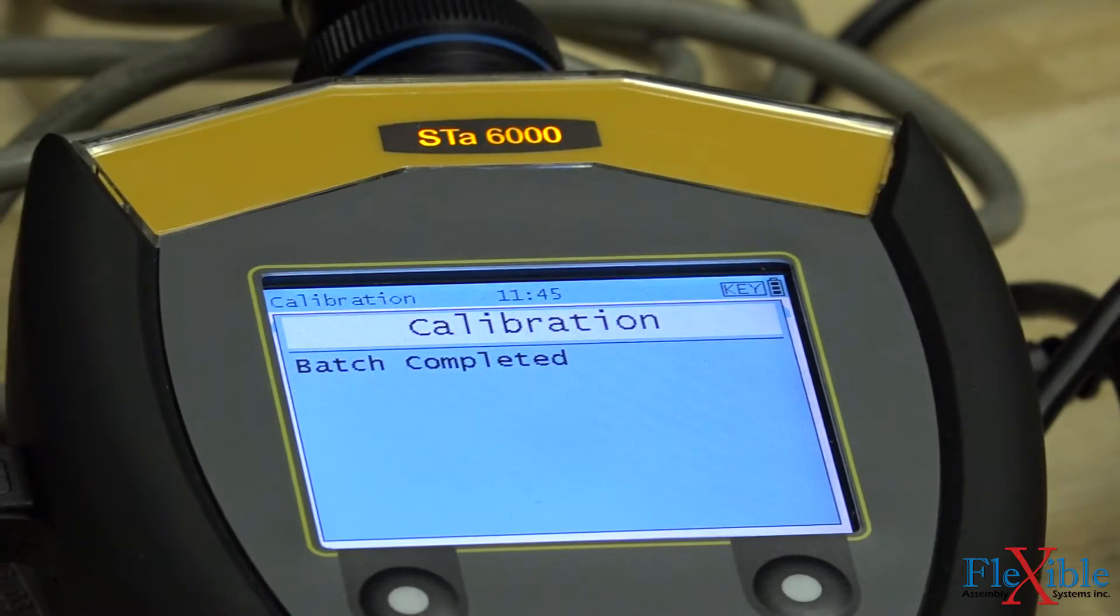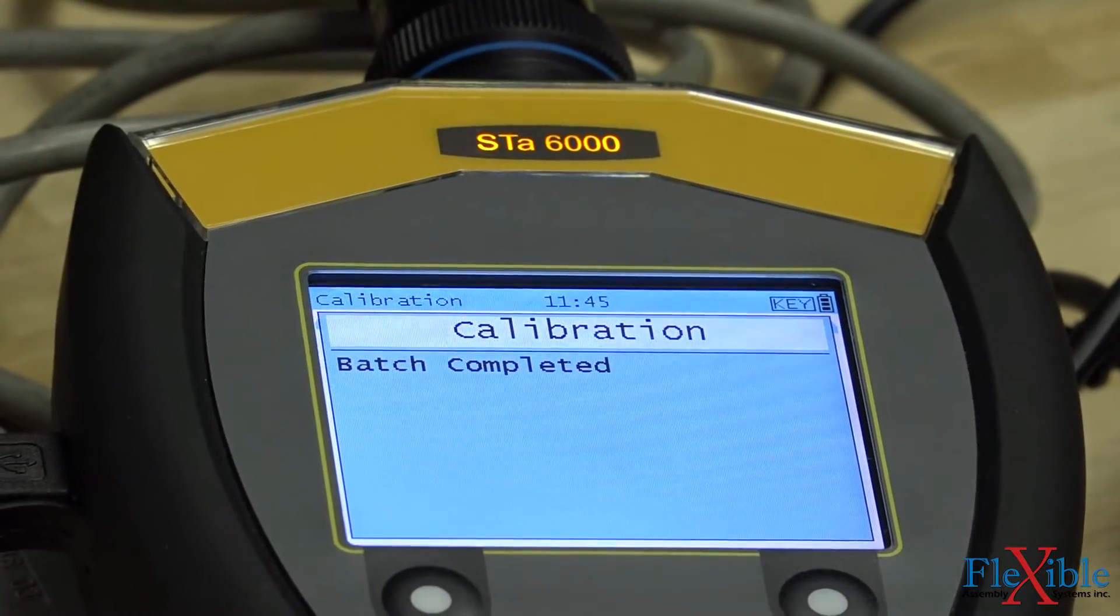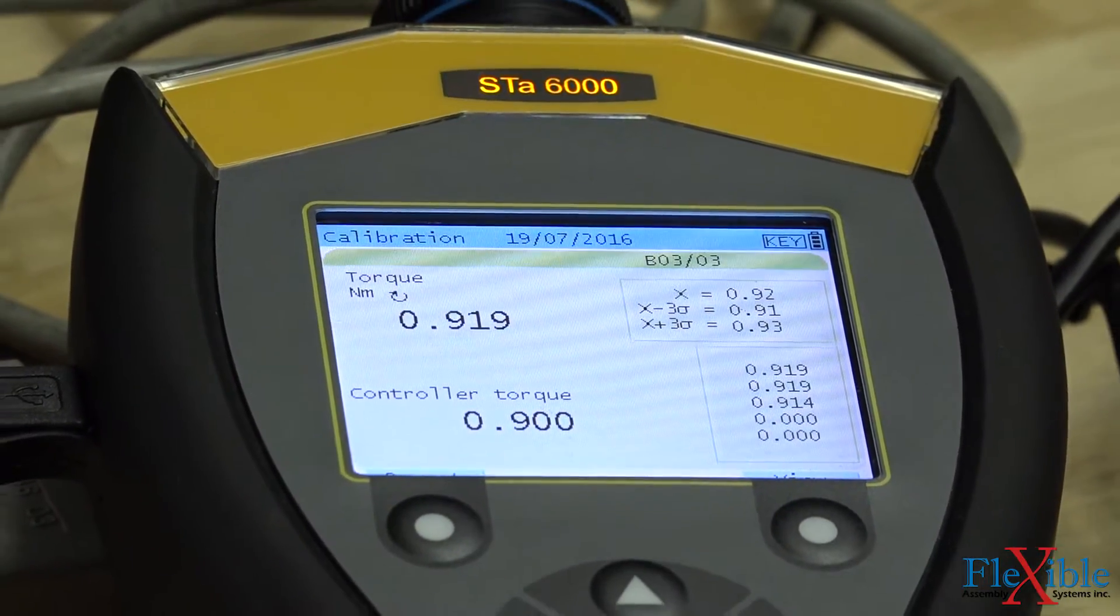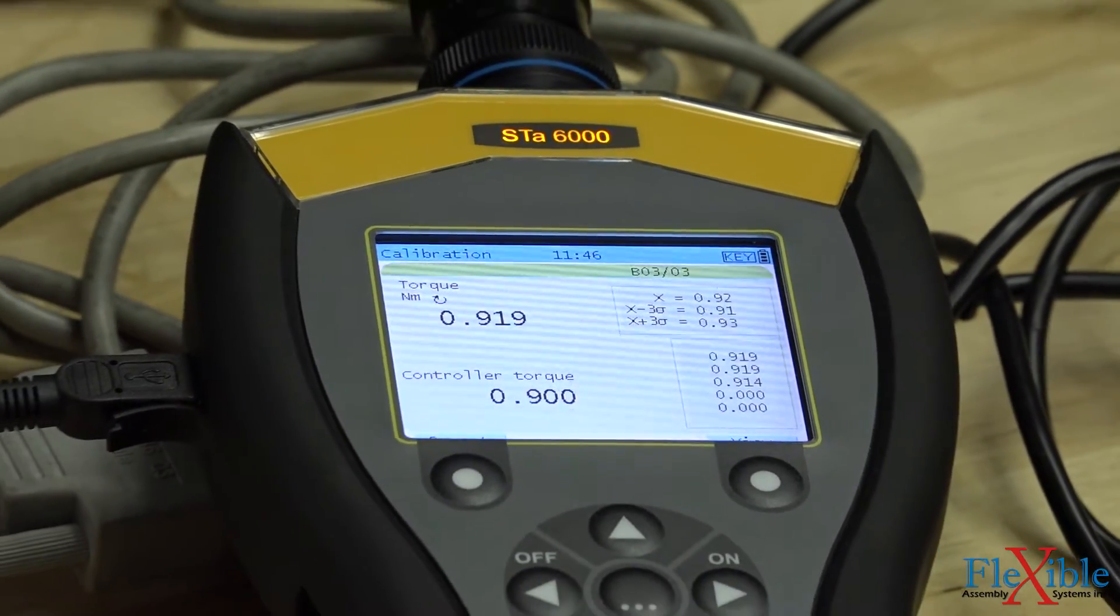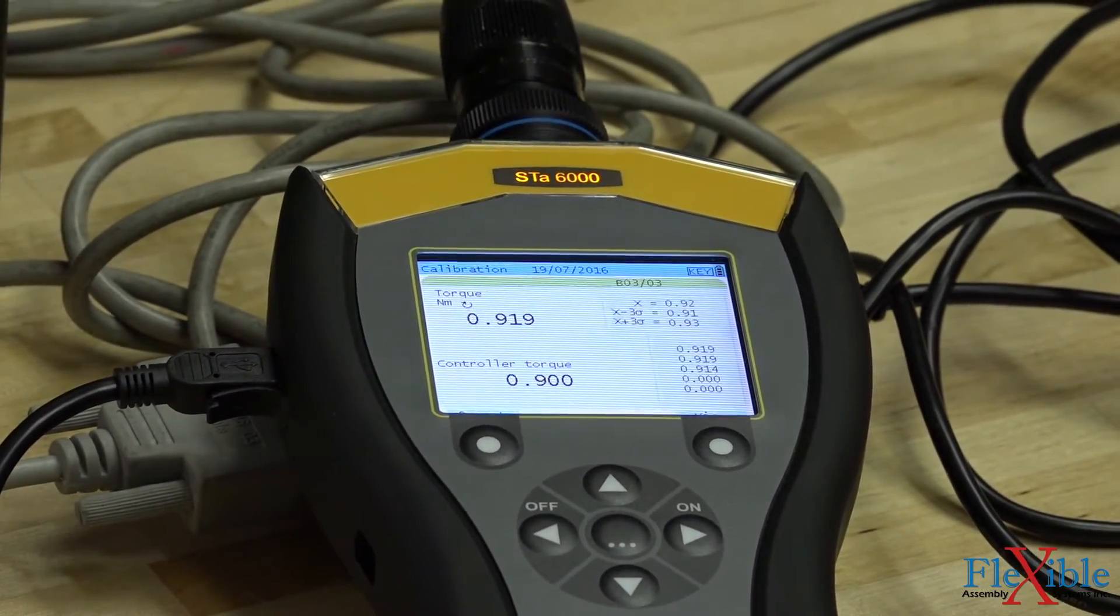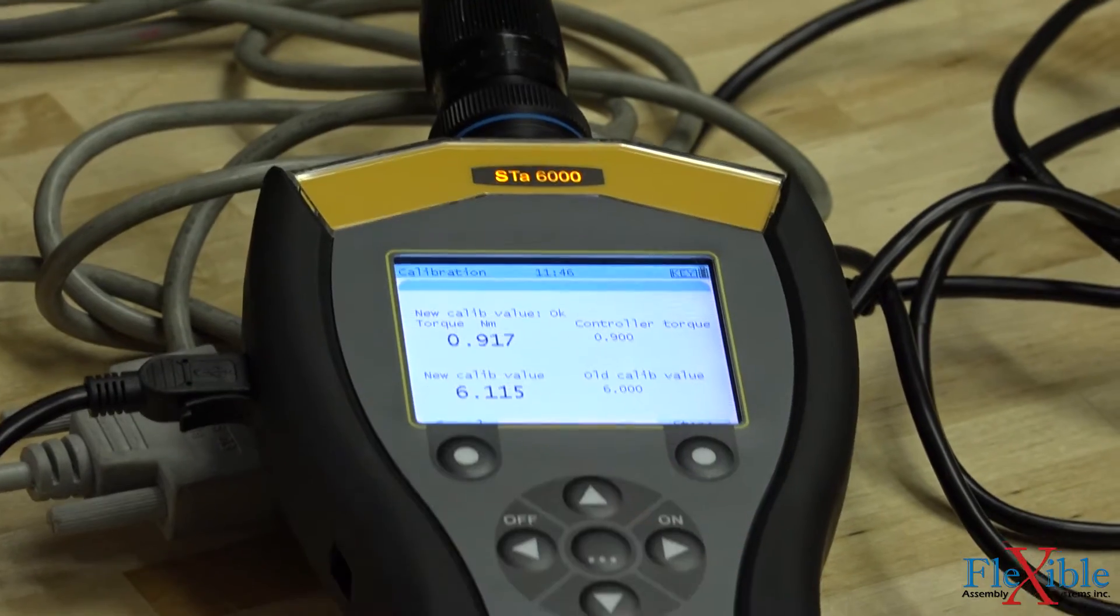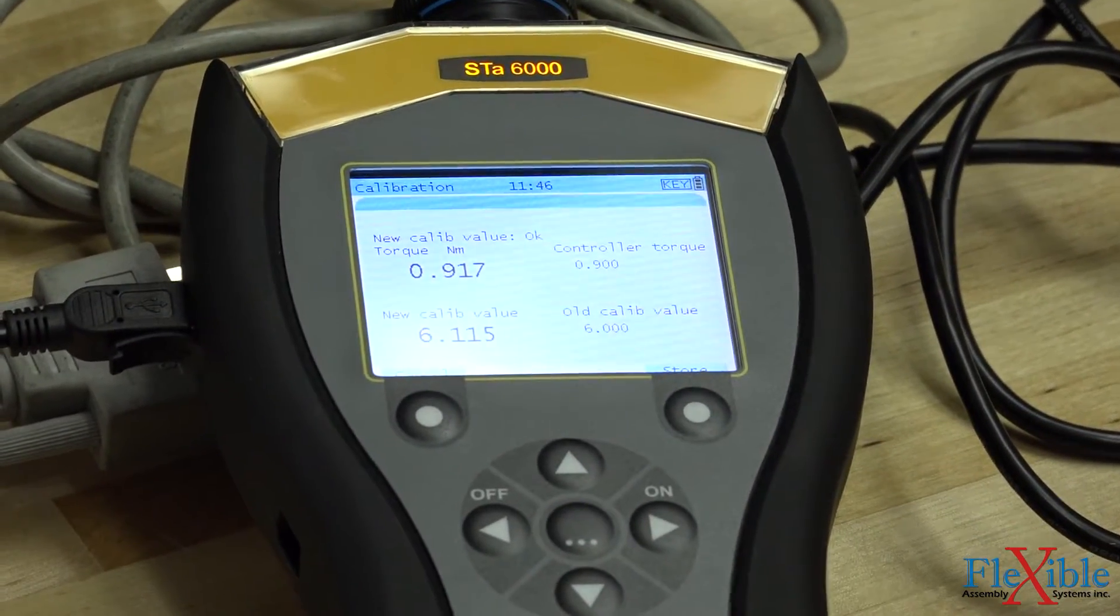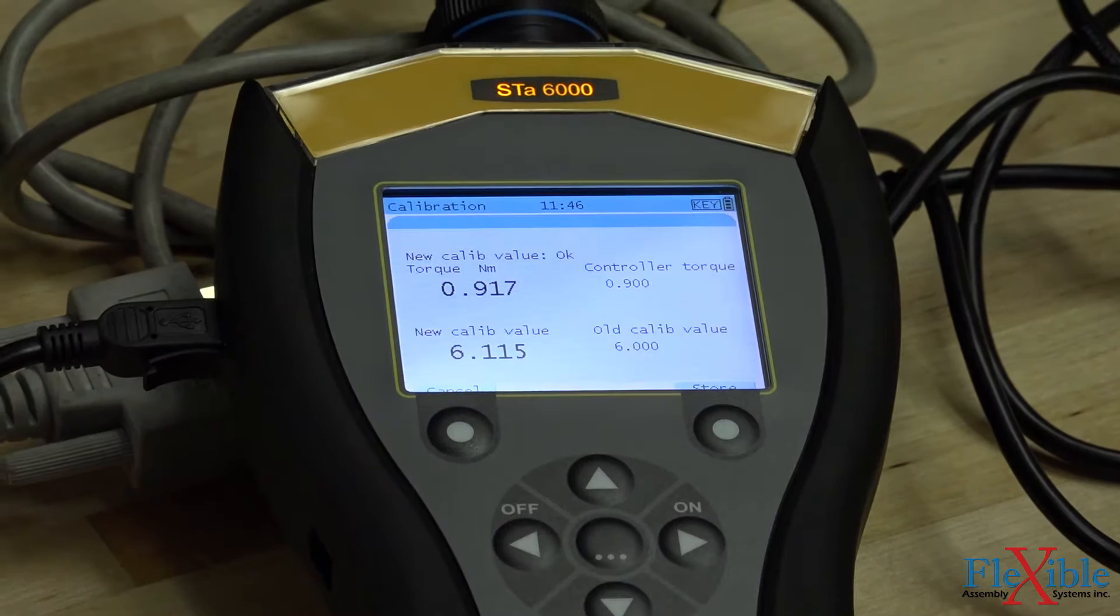As you can see, our controller and transducer values are very close together, well within our 5% tolerance. This tool doesn't need its calibration value changed, but we will do it anyway. By hitting the top left button, we now see our old calibration value and what the analyzer suggests we update it to.